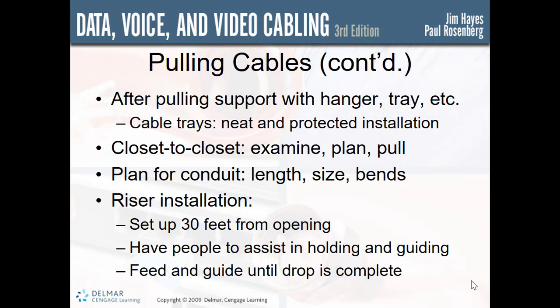When you're doing conduit pulls, when we're sending our cable through a conduit, you want to put a protector on the end of the conduit because in many cases the end of the conduit pipe is burred and abrasive and can tear your cable. And if need be, use a lubricant on the cable so that it slides through much easier. Make sure that your conduit is open on each end. Examine the ends for roughness. If need be, put tape on the end or a plastic protector. Send a string down through the line, attach your string, and give it a pull.